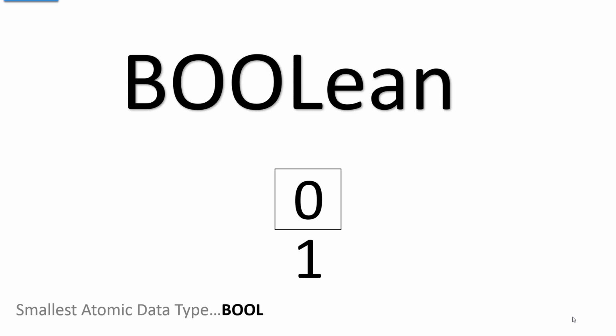A Boolean data type is going to occupy 1 bit somewhere in memory. That bit, however, is part of a word, and that bit has a value of 0 or 1. That is the limit of what you can do with a Boolean data type. In PLCs, there are not Boolean data types, but you can use a bit from a word to address that bit with the name of the word and then a delimiter and the specific bit. So there are no Boolean data types in most PLCs, but it is an atomic data type, 0 or 1.